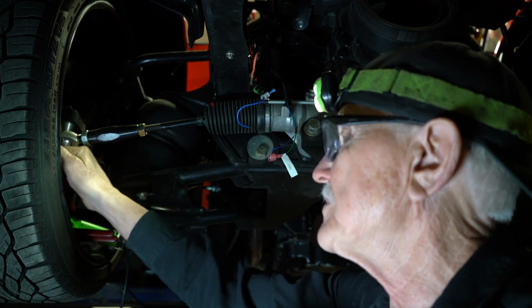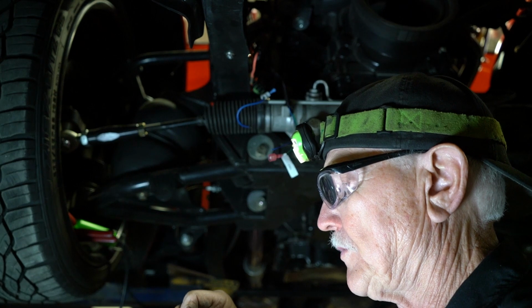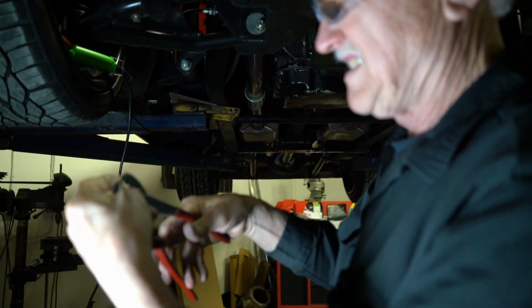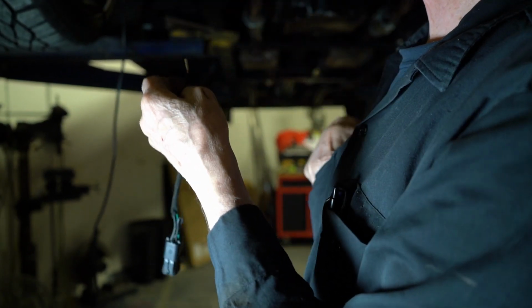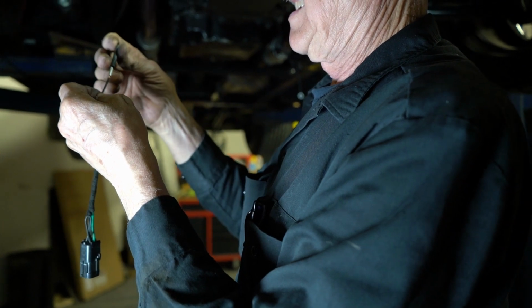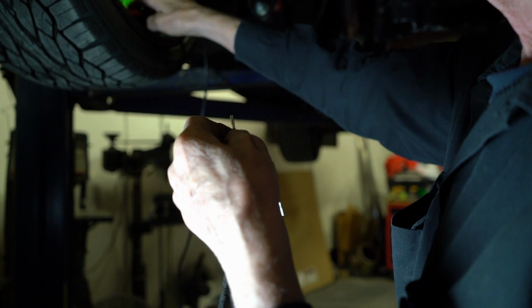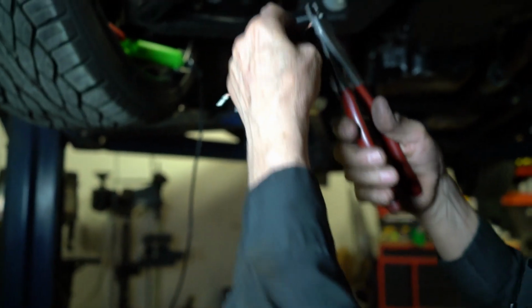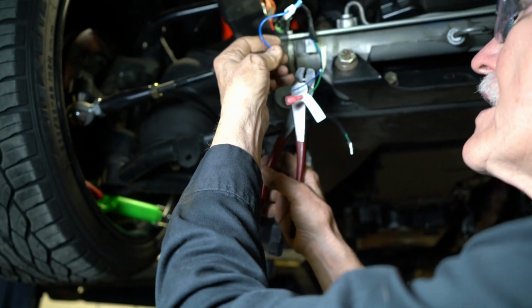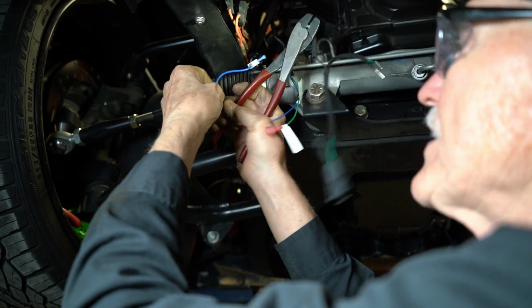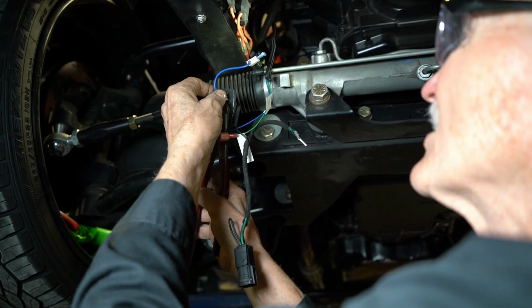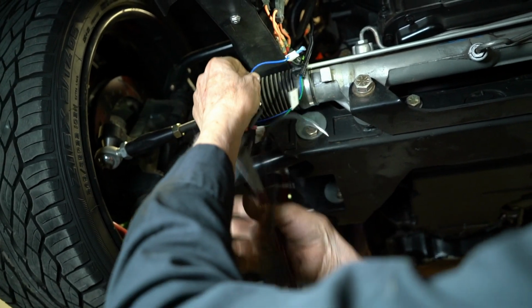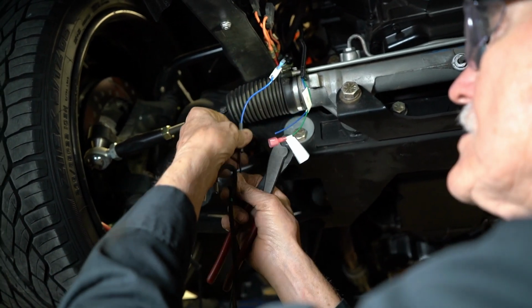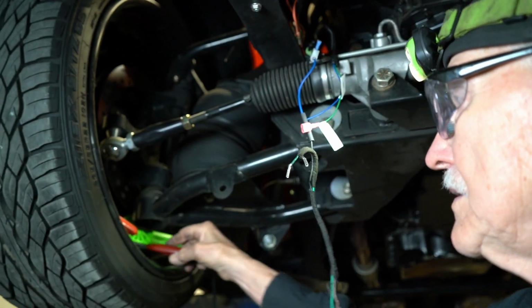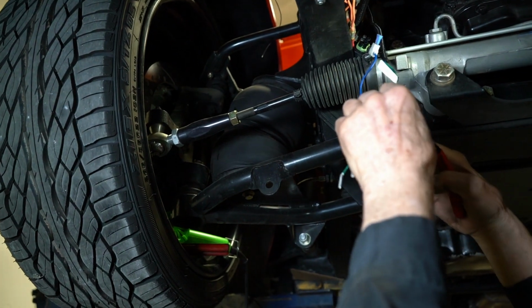Right now what we're going to do is hook up the fan trigger for the relay. The relays turn on the fans with temperature. There's 2 settings in our handheld, and also they come on with the air conditioning. So they are wired so our system provides a ground signal only for a relay, not enough to ground the fan itself. That has to be a whole separate ground through a big heavy wire. But the nice thing is you can set the temperature you want it to come on right on the handheld. You don't have to have somebody program it for you.